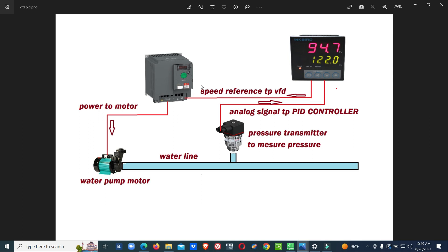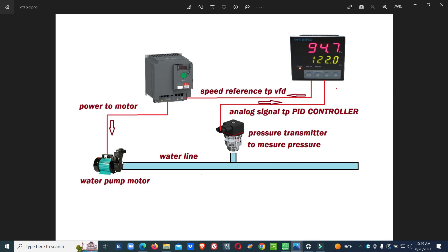To address all these issues, the PID controller was implemented. The PID controller adjusts the speed of the pump to maintain the pressure. The pressure transmitter continuously monitors the pipeline pressure and feeds the pressure feedback to the PID controller. Based on that feedback, the PID controller gives a signal to the VFD with a speed reference to control the pump. This way the pump never stops — it only increases or decreases speed to maintain the pressure in the pipeline.